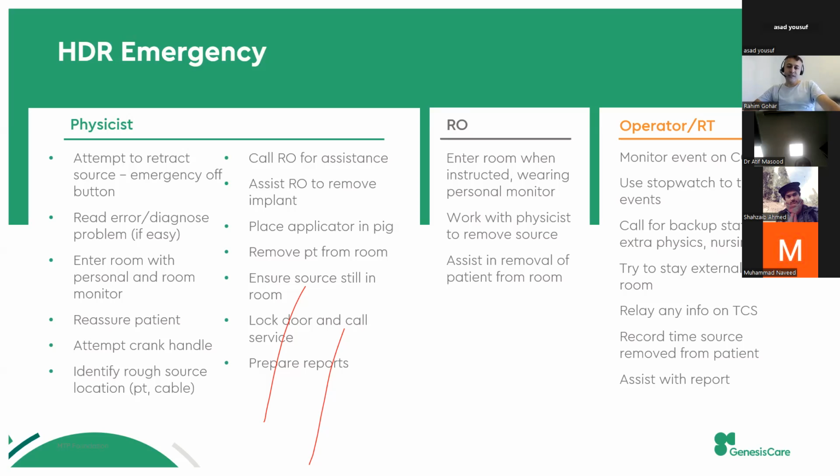Yeah, that's true. Also, time management is there. One personnel is not supposed to spend all the time inside the bunker. We can shift between the RTT, the physicists, and the doctors. And the drill is very important, so that everybody knows their function, the work they have to do during the emergency. Use of the stopwatch, sometimes we are ignoring this. We have seen that we are not really doing this practice. Very difficult. We even used to not use the survey meter at the console.